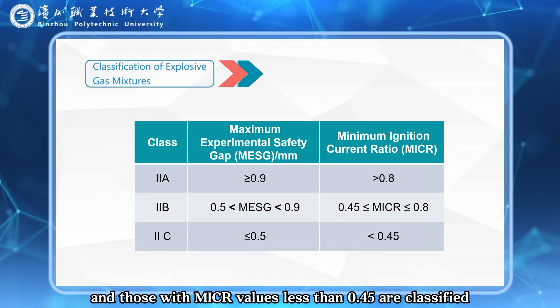as Class IIA. Those with MESG values greater than 0.5 mm but less than 0.9 mm are classified as Class IIB. And those with MESG values less than or equal to 0.5 mm are classified as Class IIC. Explosive gas mixtures with a MICR value greater than 0.8 are classified as Class IIA. Those with MICR values greater than or equal to 0.45 and less than or equal to 0.8 are classified as Class IIB. And those with MICR values less than 0.45 are classified as Class IIC.